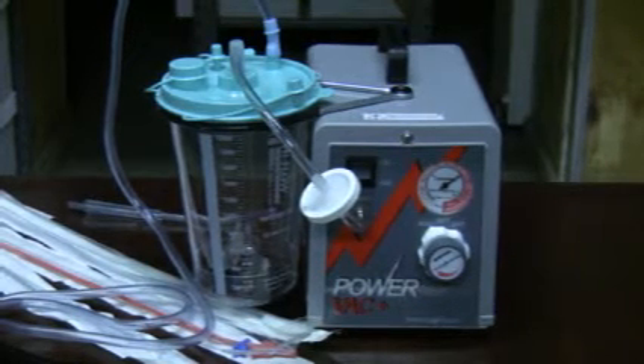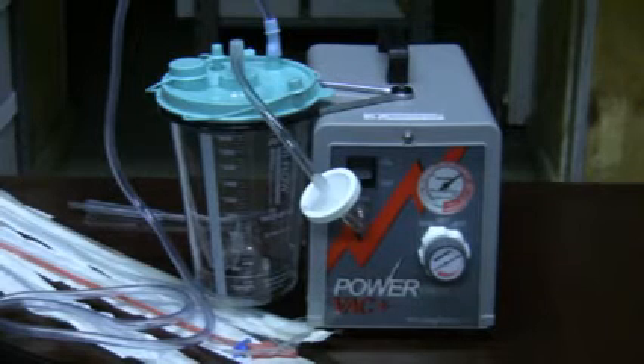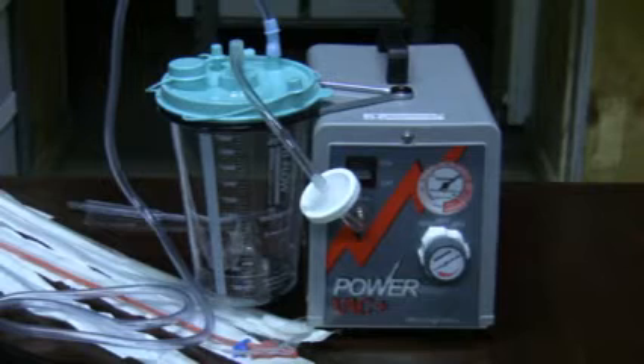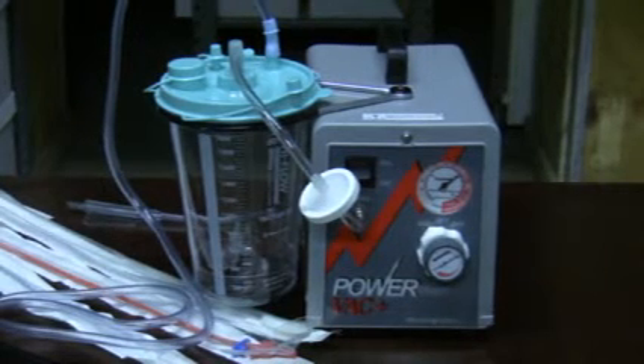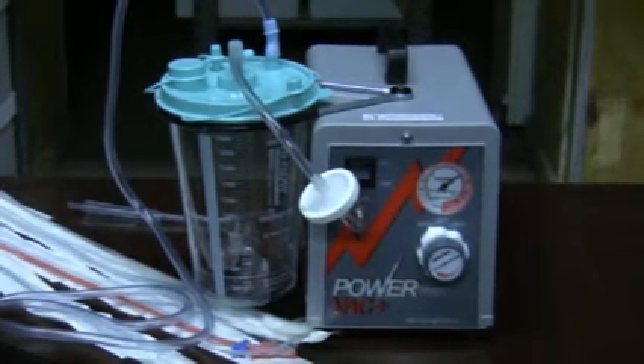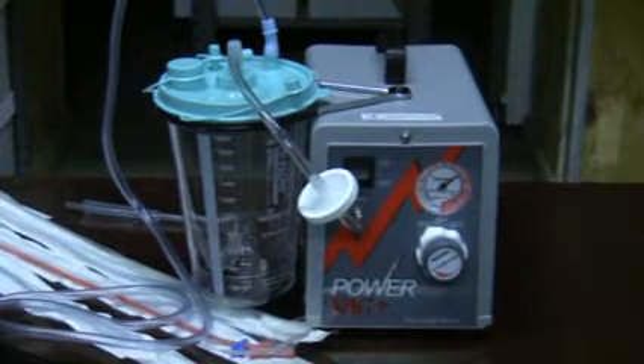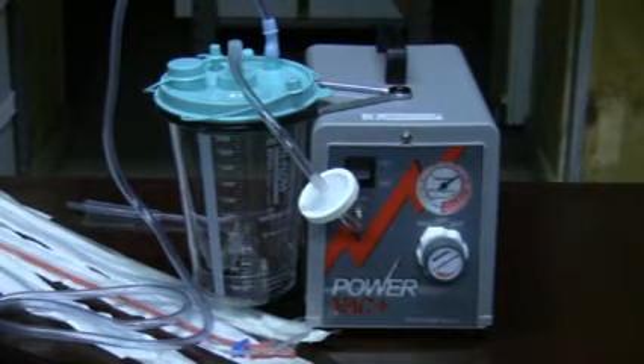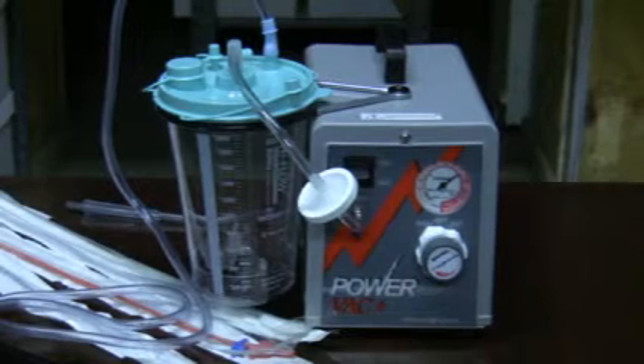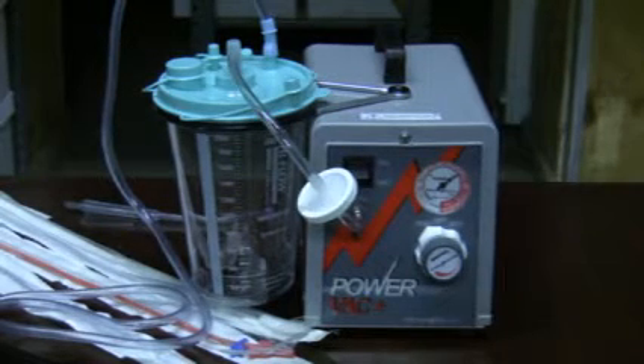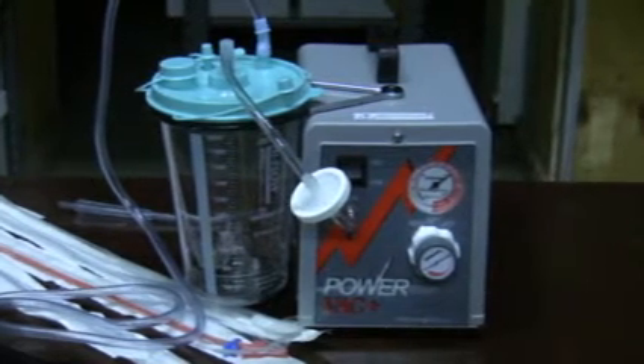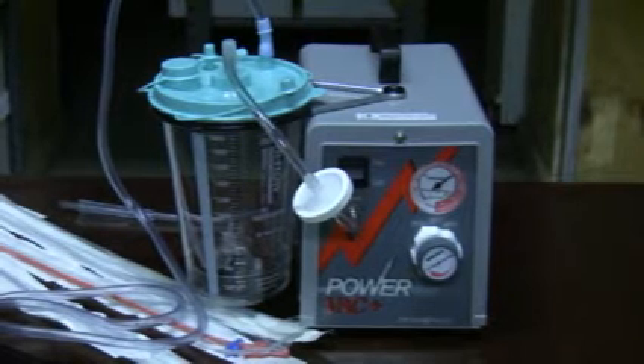You would want to allow 15 minutes to pass, allowing your intermittent suction machine to cool. After it has cooled, then you may go ahead and power back on. If when you power back on after 15 minutes, your intermittent suction machine functions as normal, it is okay to proceed with your suction procedure.